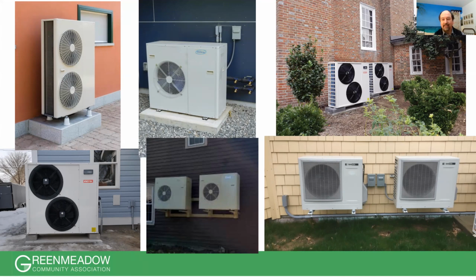Well, the selection of the heat pump, for heating and cooling, depends on the heat gain and heat loss of the house. I think it was Tony talking about coming over and trying to help figure out how to make the house more comfortable. It's really important, in order for these heat pumps to work effectively, that the house be well insulated and the windows probably upgraded, because these things are relatively low output compared to the boilers that these Eichlers are accustomed to.